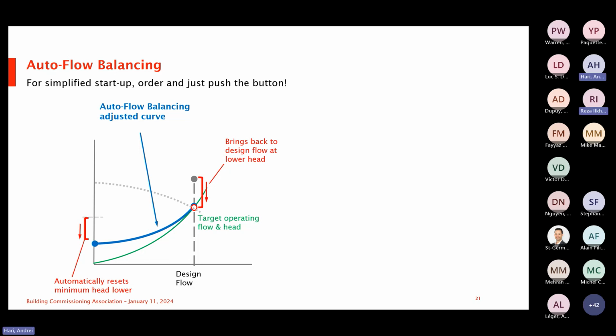Yes, Andrew, we can discuss this after this, but just let me place my question here. In the traditional approach, we had one differential pressure sensor at the end of the hydraulic line, so once the pressure was being kept constant, if one unit, one load at the vicinity of the mechanical room closes, the flow actually decreases, but we keep the differential pressure constant, so the furthest hydraulic point would still receive enough flow or enough pressure, right. Yeah. But in this approach, since the head decreases, our furthest point may not receive enough flow only because the head pressure is not high enough.